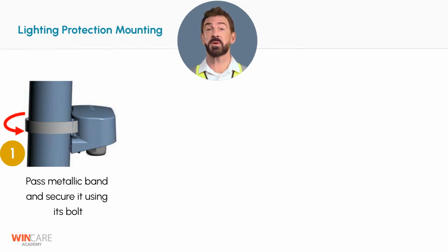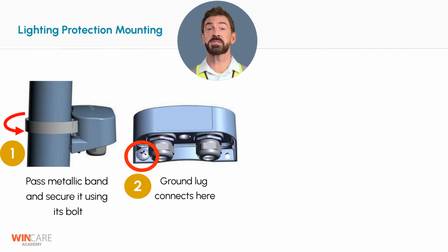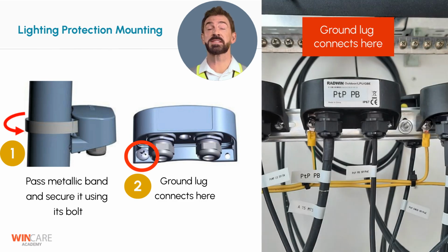To mount the lightning protection unit, start by inserting the metal band through the mounting slots. Next, secure the unit firmly using its bolt and attach the ground connection to ensure proper surge protection. In this example, the unit is installed indoors, inside a rack on a flat surface using screws. Because of this controlled environment, weatherproofing is not required. However, for outdoor installations, always seal all connectors to protect them from moisture, dust, and other environmental elements.